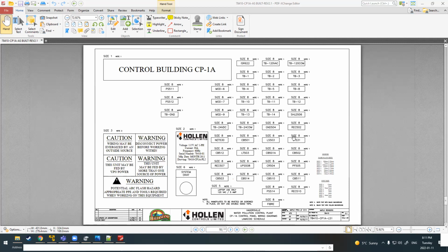This drawing right here is called a Lamacoid schedule. You won't find that everywhere, but it really just lists all of the little tags that will show up on the panel, for the manufacturer. So this is the front of the panel. This one's going to give you your rating for it. This is probably the only one, this one and the power one, multiple sources of power, that hopefully are on every panel that you guys go into. The electricians probably know that that's not true for every panel. These other ones are labeling the different devices inside the panel.